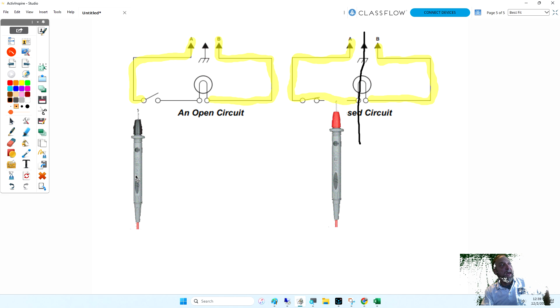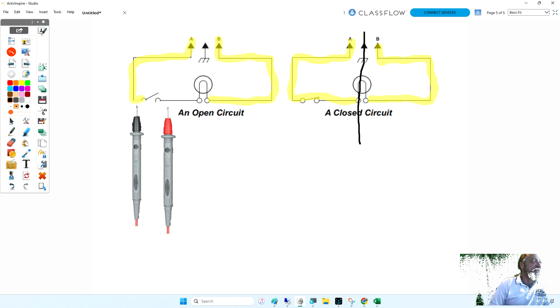120 is correct, but why do we have 120? Line 1 comes in but stops here. In the circuit, when the load's working, the light bulb separates line and neutral. But when there's no current flowing, the part inside the light bulb is just a piece of metal like the wire. So if neutral's connected to that bulb and it's not running, neutral comes all the way back up to the switch, and that's why we'd actually have a voltage reading.